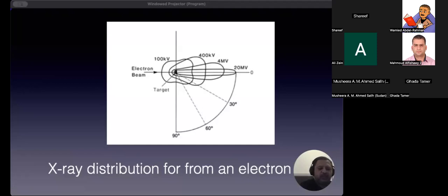And this, I think, is now obvious to all of you: how or why we construct, for example, an X-ray tube in such a way, the target and the beam with respect to the patient, whereas in a linear accelerator, where we're interested in producing megavoltage beams, the electrons are actually shooting towards the patient. So we put the target between the electrons and the patient.